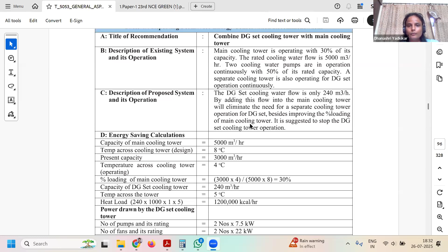Already your main cooling tower is only operating at 30% loading. You are just shifting your DG set cooling tower load of 240 meter cube per hour to the main cooling tower. So this improves the percentage loading of the main cooling tower, and it is suggested to stop the DG set cooling tower operation. So here is the energy saving calculation for this scenario.